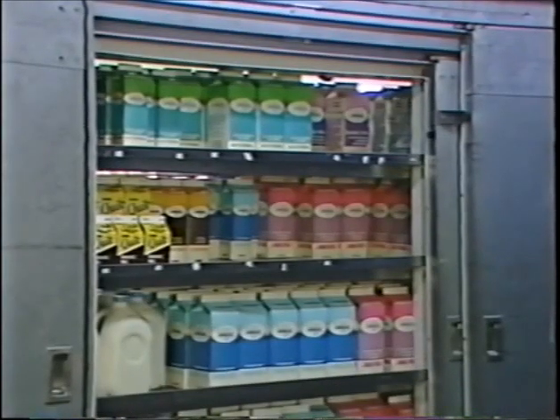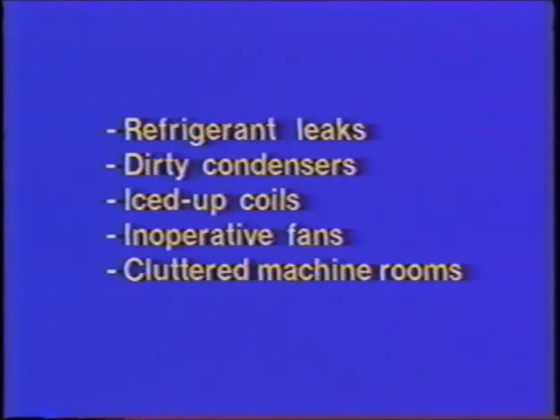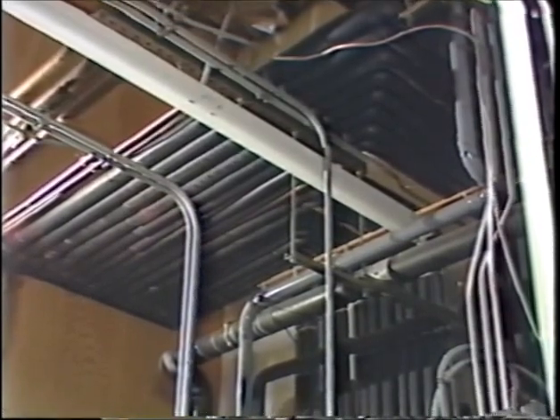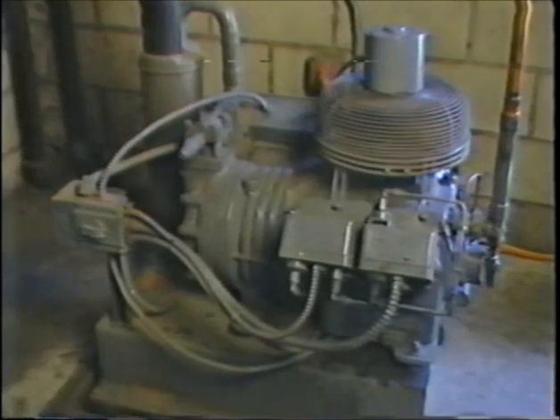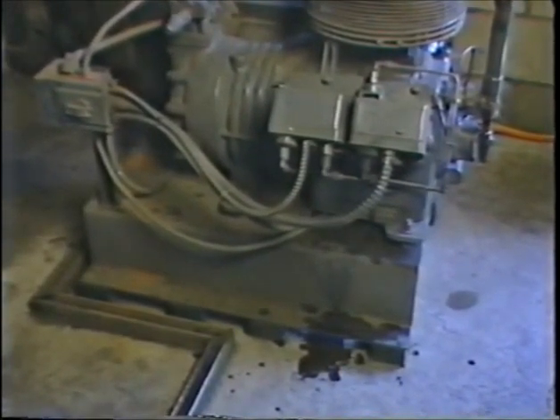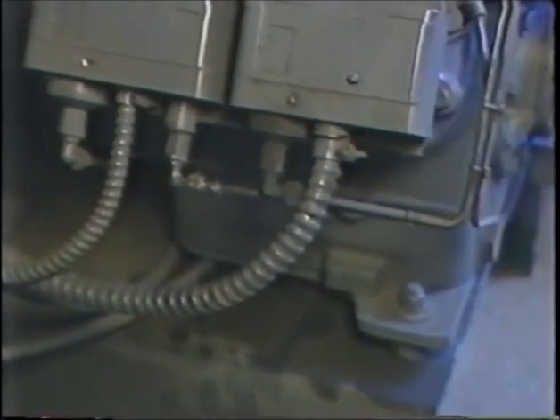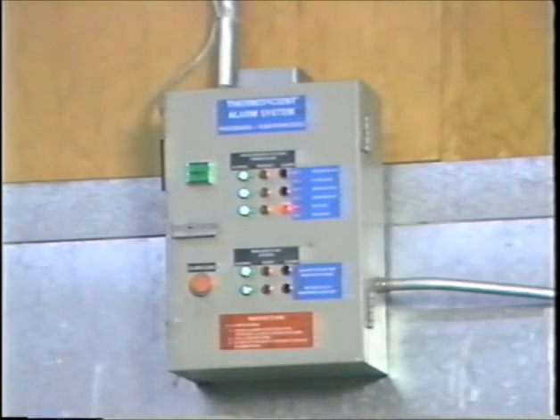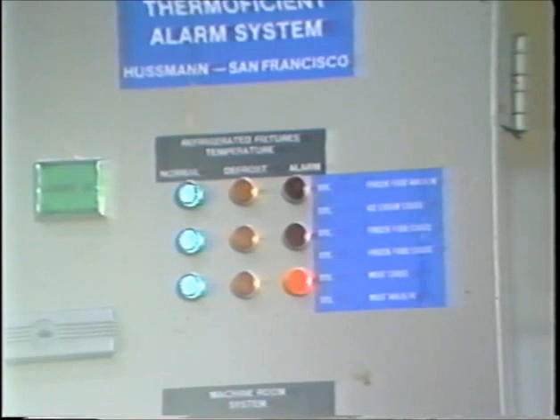Some of the other things that can interfere with an efficient refrigeration system are refrigerant leaks, dirty condensers, iced-up coils, inoperative fans, and a cluttered machine room. Refrigerant leaks are the second most expensive maintenance item in supermarkets — a compressor replacement ranks number one. But often a leak can be spotted visually before it causes real problems. Some of the telltale signs are bubbles in the sight glasses located in the liquid line coming out of the receiver, or fresh oil in the compressor room or any place where your refrigeration lines run. If you spot a leak, notify your store manager. A properly operating refrigeration alarm system can save thousands of dollars — dollars which affect your store's profitability and you.